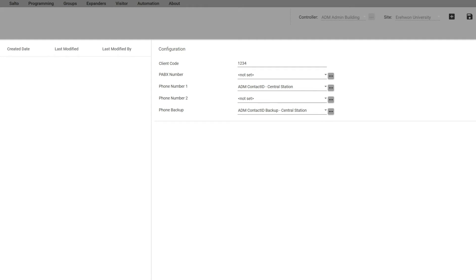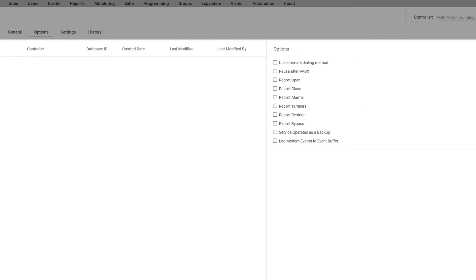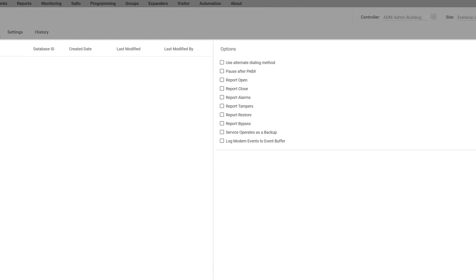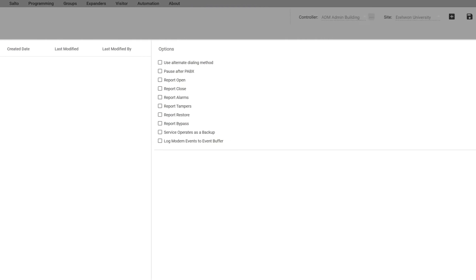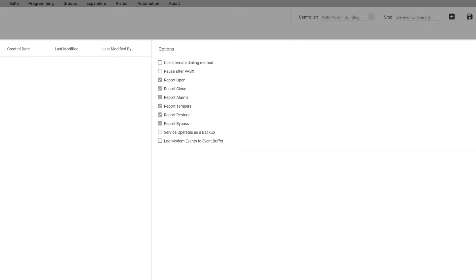You really have to be careful here to click on what things you want to report out to that central station. So we recommend clicking anything here on the options that says report. Report open inputs, close inputs, whether it's armed or disarmed, whether there's alarms, any tampers, and then when it restores, and also bypass. Those are things you do want to add.